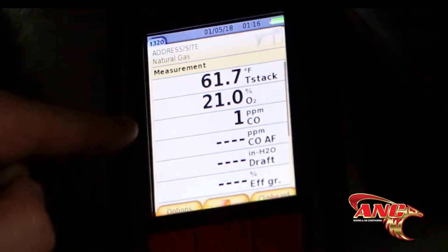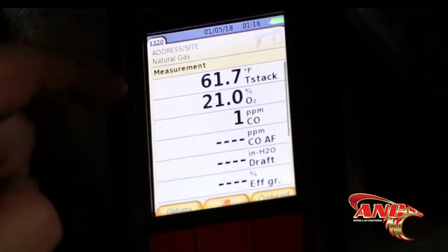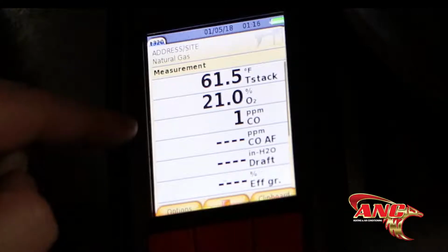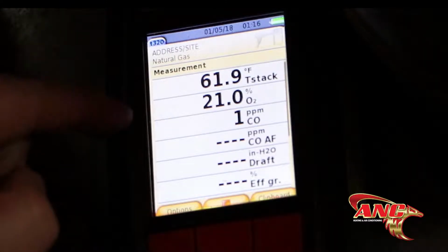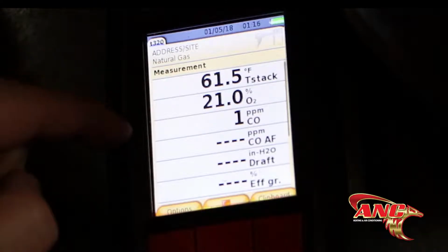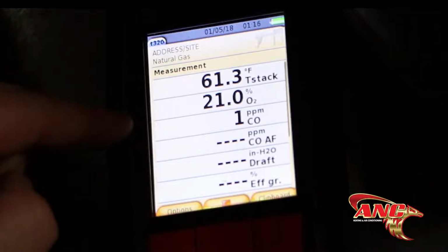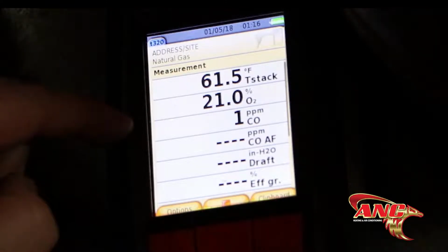The third is the big number. That's the one everyone's scared of. That's carbon monoxide. Now, in the flue pipe, we have an acceptable amount of carbon monoxide. We're going to usually see anywhere between 15 and 45 parts per million in your flue. If it gets over 100, we know there's a problem. It's probably a minor problem. Dirty burners, gas pressure, etc.